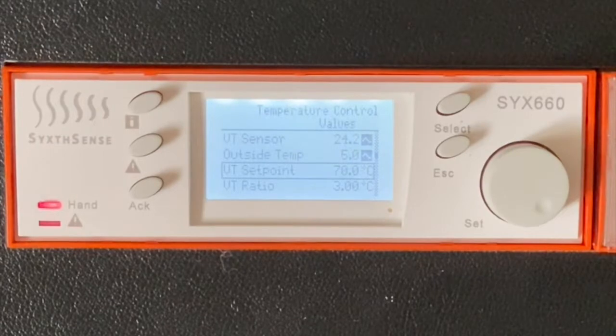So what I would then do is go and inspect the radiators in that circuit, make sure they're getting warm, especially warm where the room sensor is located. It's essential that the placement of the room sensor is in a heated location in order for the optimization to function correctly. And we want to make sure that those TRVs are turned up to maximum, and we want to make sure that that flow temperature is actually being sent and received at those radiator locations. Okay, that's about it for now.